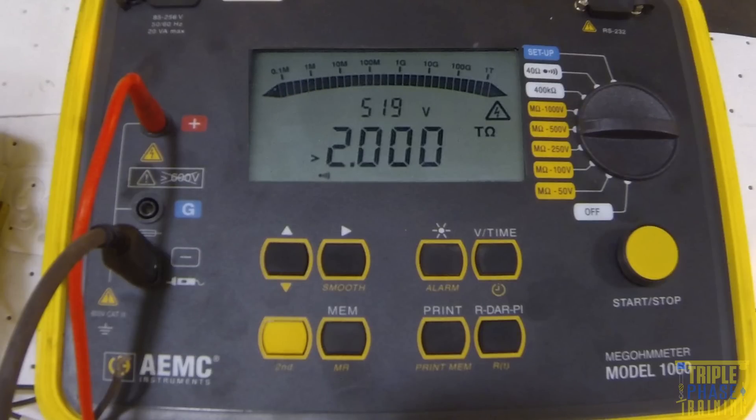The brand new H-Class motor quickly displays a reading greater than 2 tera ohms. That is the highest resistance the 1060 can measure. With a reading of greater than 2 trillion ohms, you can be confident that the motor is good.